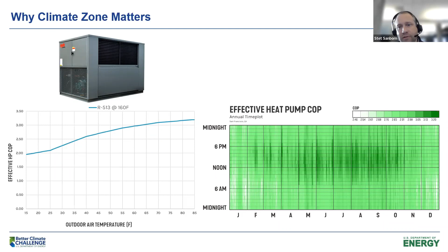The COP we'd expect for this building, delivering between 150 and 160 degree water from an R513 refrigerant, ranges all the way from 2.4 up to almost 3.5. So we see a pretty big variety. In a colder climate, you could expect this to get down into the 1.5, 1.6 range for COP.